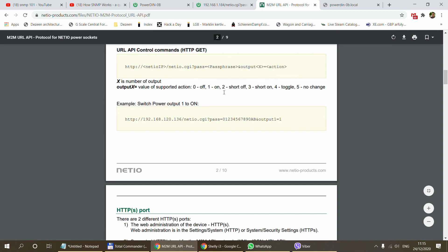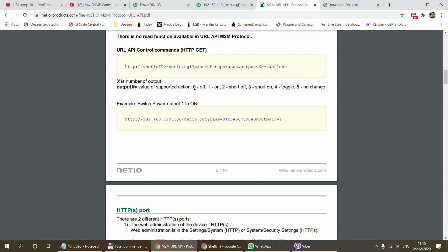The action is also a number. Zero means the output turns off, one means the output turns on, two is a short off — so it's on and then it turns off and goes back on, which is useful if you want to reset the device. Three is the opposite, a short on — it goes on and then turns off. And four is a toggle.